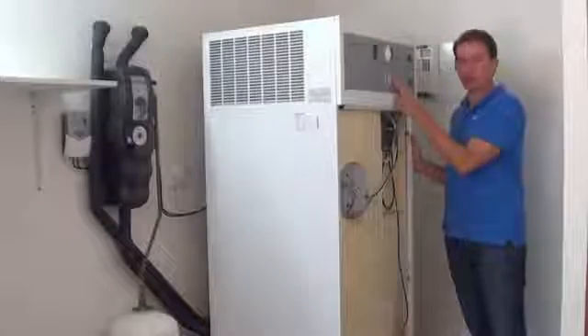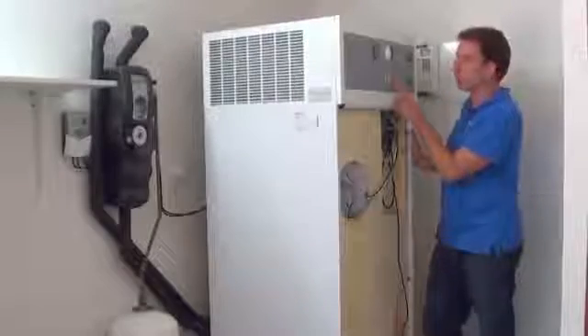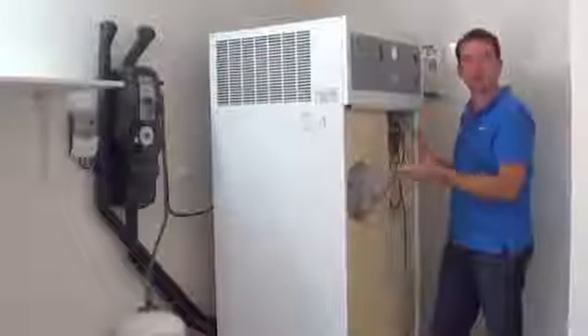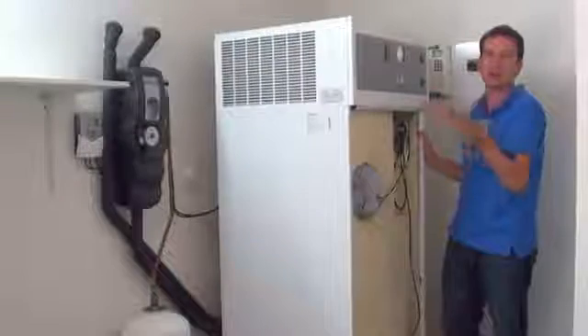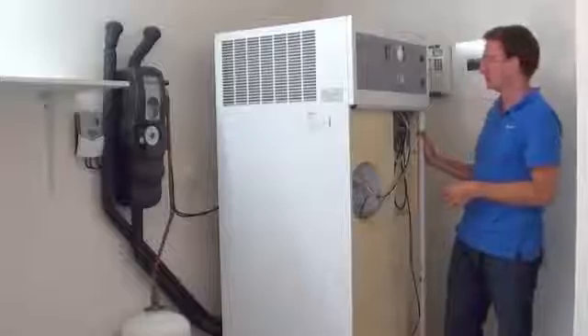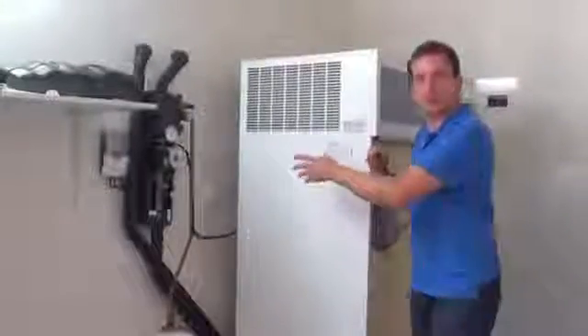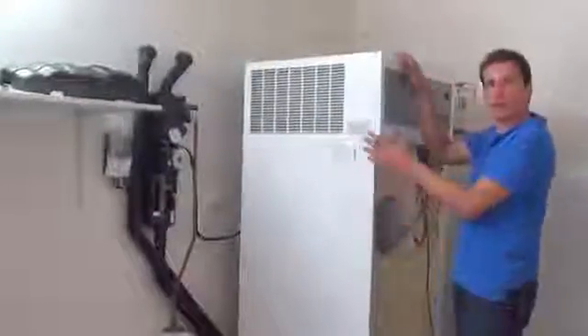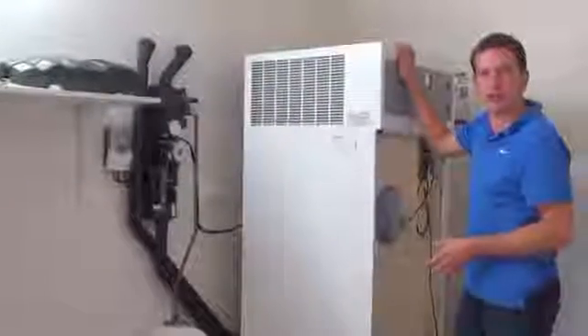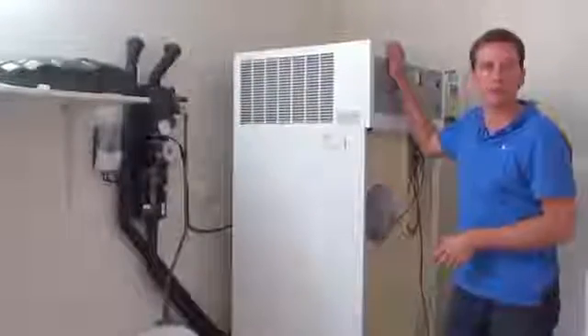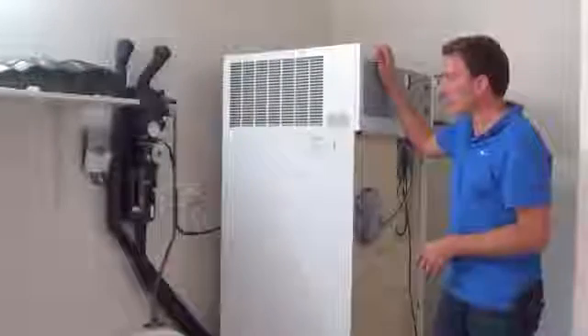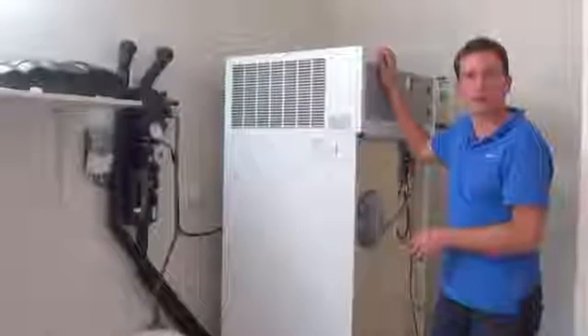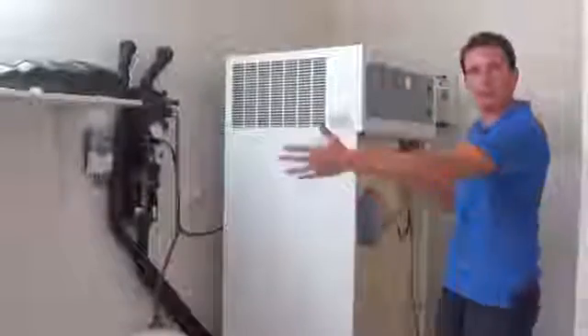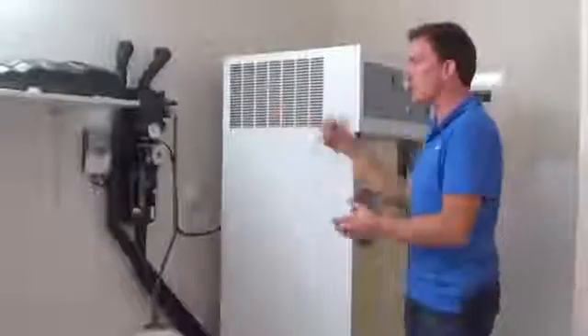Alright, and an additional feature, we've got a timer in here, a day or a weekly timer that can switch on this element so that it can automatically kick in and raise the temperature once every, say, 2 months to kill off the bacteria. Then you've got your normal temperature setting over here where you can adjust the temperature of the heat pump. So basically what I've shown you today is a combination of solar and heat pump and integral system. This is the smallest system that we can offer, which we use for families of 4 or less in a house system. If we want to go and do hotels or bigger systems, commercial systems, we have to split the heat pump, and we provide individual tanks with heat exchangers that marry these two systems.